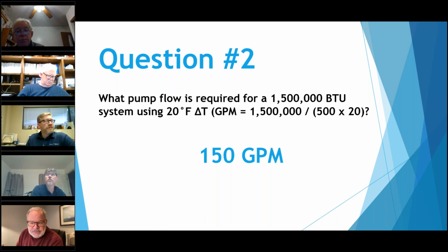Okay, guys, that's your second question. Make a note of that. What pump flow is required for a 1.5 million BTU system using 20 degrees delta T? The answer is 150 GPM. You're going to have to type it in, guys. 150 GPM. Back to you, boss.